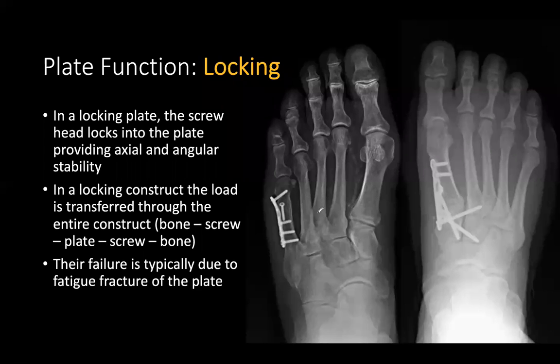In locking plates, the screw heads lock into the plate for axial and angular stability. It doesn't matter if you catch one cortex or two — the screw locks into the plate and acts as a stable construct. In a locking construct, the load is transferred through the entire construct instead of just between the bone and screw. Failure is typically due to fatigue fracture of the plate — when a locking screw breaks, it's usually at the interface between the plate and the screw.